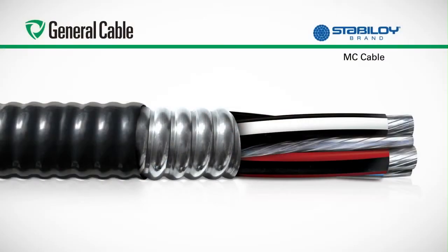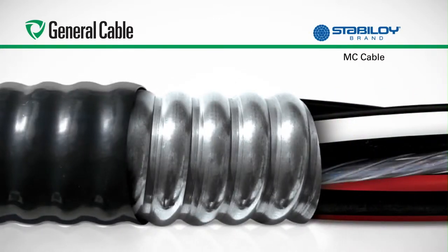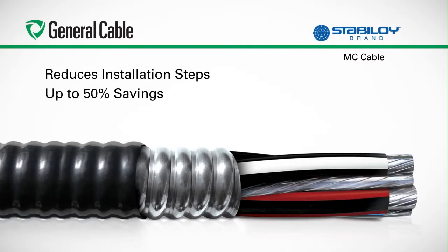The owners like it because it's less expensive than copper, and we've had no callback issues. General Cable's MC Cable features three or four phase-identified XHHW-2 conductors, plus a bare equipment grounding conductor assembled inside interlocked aluminum alloy armor. The armor eliminates the need for conduit and protects the conductors from damage during and after installation. Stabiloy brand MC Cable's all-in-one assembly drastically reduces installation steps, with savings up to 50% over traditional pipe and copper installations based on an RS-Means study, and it reduces the risk of damage to the conductor during installation.